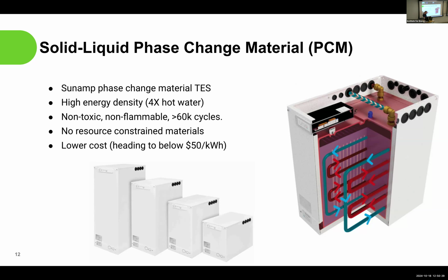So yes, in very hot climates, and in a situation where you're trying to store coolant at 5 degrees C, you will see thermal losses. But what we're trying to do here is shift typically within a few hours in a day—generate coolant in the morning, say, and use it later in the afternoon, or at 4 o'clock. Or maybe you're using some of the excess capacity in the middle of the day and shifting it by 3 or 4 hours. So the thermal losses over those time periods are not huge. If you were trying to keep this for days and days and days, yeah, totally, that would be an issue.